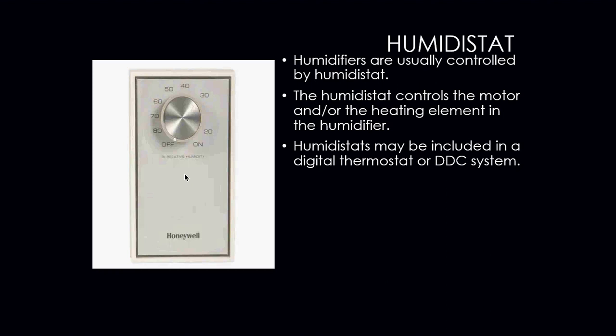One way we need to control all of our humidifiers is we need to install what we call a humidistat. Yes, that's correct, humidistat. Not a thermostat, humidistat. Humidifiers have to be controlled by some sort of switch that is able to measure the relative humidity in the space, and those are called a humidistat. Okay, humidistats control the motor or the heating element in the humidifier. Humidistats may be included in a digital thermostat. Some of them, depending on how expensive you want to be, can have a humidistat installed already on a thermostat, or can be a DDC type of system.